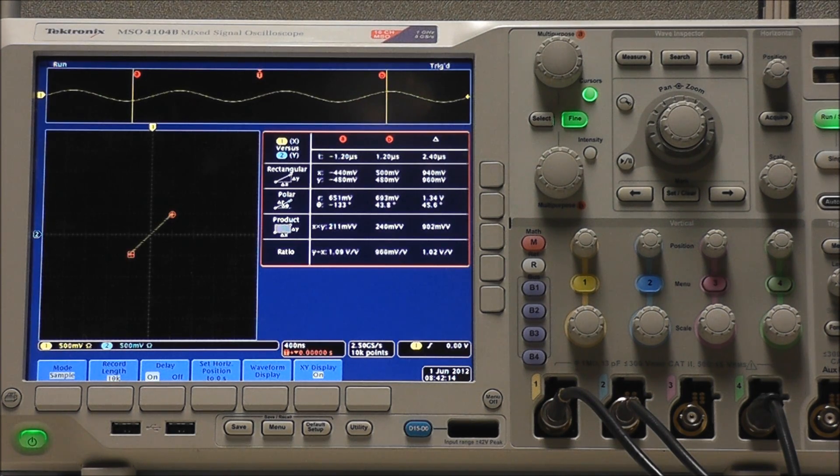Our four XY cursor readouts show us rectangular and polar coordinates, as well as product and ratio. As you can see, we have a nice straight line with a ratio of approximately 1 volt per volt. This tells us that the waveforms have equal frequency, amplitude, and are in phase.